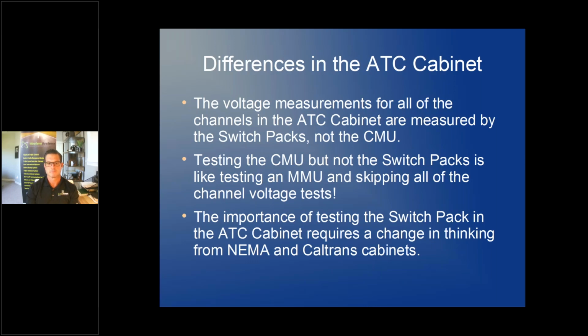We did not combine the CMU tester and the switch pack tester into one device because, for one, you would have a very large object, and if you had a low voltage cabinet, we'd be forcing you to buy a switch pack tester you couldn't use. Also, if you had them both in one device and that device had a problem, you'd have to send the whole thing to us and wouldn't be able to do any testing at all.